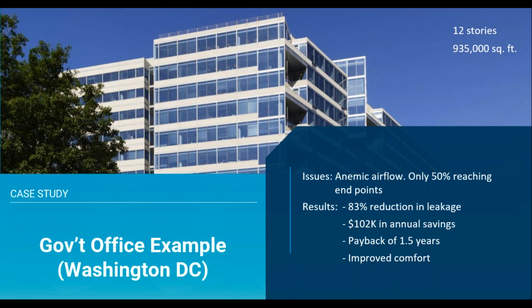I was going to go through a few case studies on how this all worked. This is a large government office building in Washington, D.C. They had a large shaft that was incredibly leaky, and only 50% of the air was actually reaching those endpoints. We were able to get them measured savings, which they verified themselves, of $102,000 a year just by sealing up the ductwork in that one shaft. The payback was less than 2 years, around 1.5 years, and it also improved comfort in the building, because as you can imagine, if the air wasn't making it to those endpoints, it was hot in the summer and cold in the winter. We were able to solve all of those problems for them.